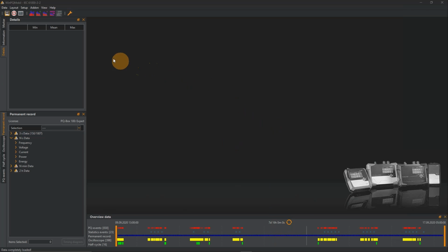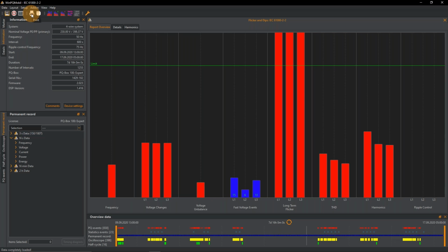The next step is I will go to this icon, norm evaluation, to get an overview of my limits according to the standard I've chosen before. And I want to see, okay, is everything fine or not? I see frequency is fine. The red bar indicates our measurement values, minimum value and maximum value, respective to the limit value. So this display is normed to the limit values. I see frequency, no problem. Voltage changes, no problem. But if I go to long-term flicker, I see there were problems on phase 1, 2, and 3.